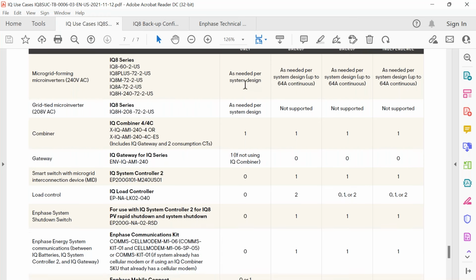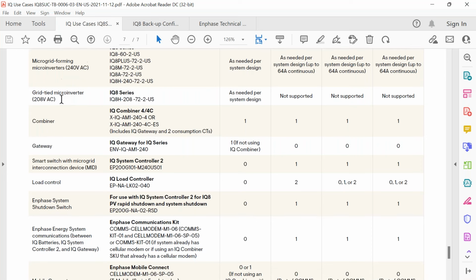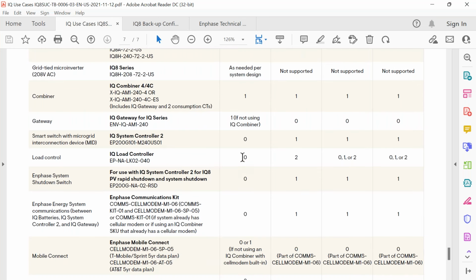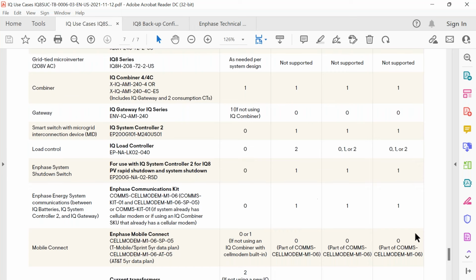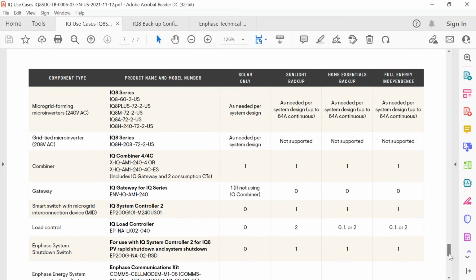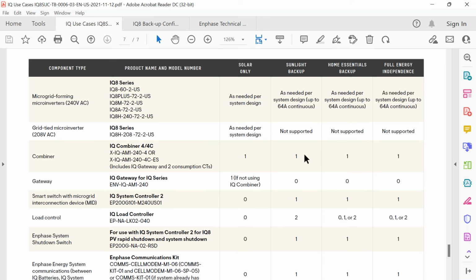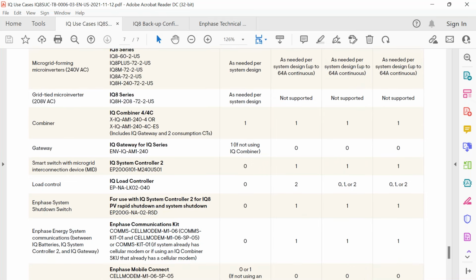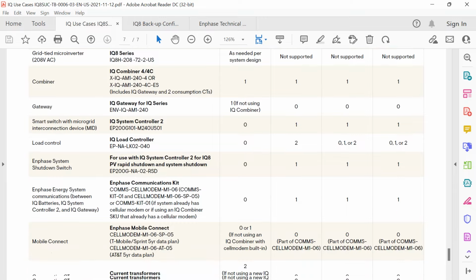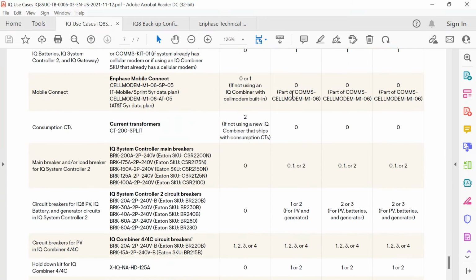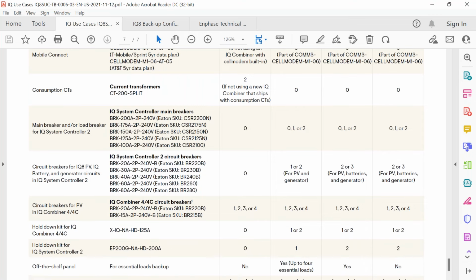For example, with solar only, you can see it tells you that you need microinverters, a combiner, but do not require the system controller, load controllers, and so on and so forth. Now, if we look at the sunlight backup column here, you can see with this configuration, you're going to need the combiner. You don't need the gateway because it's already included with the combiner. You would need the IQ System Controller 2. You would need 2 IQ load controllers, an Enphase system shutdown switch, the communications kit, and it also has additional details on the breakers that would be required for the system as well.